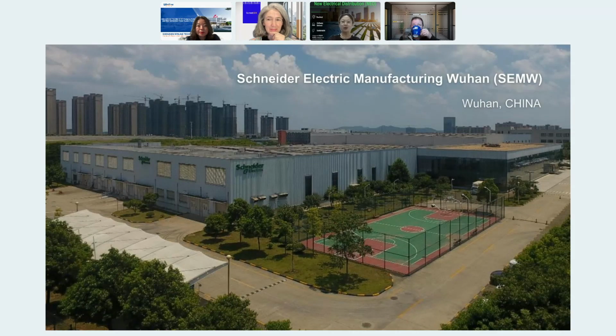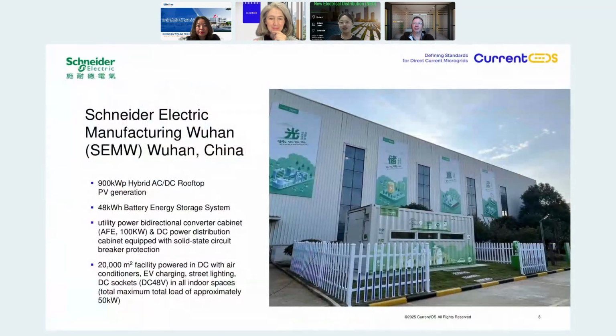I invite everyone to take a virtual visit to our Wuhan plant in China, built by Schneider Electric. By end of 2023, Schneider Electric completed this real case project with a hybrid AC/DC architecture. The total installed capacity of the rooftop PV system is about 900 kW peak, covering an area of 20,000 square meters, plus a 48 kWh battery storage system. The system includes a 100 kW bi-directional interlink converter cabinet, DC electrical equipment with distribution and solid-state circuit breaker protection, and a monitoring system. On the load side, the system covers DC air conditioners, DC street lights in the parking area, DC bi-directional chargers, as well as DC lighting and 48-volt DC USB-C sockets indoors for meeting rooms, exhibition halls, and pantries.